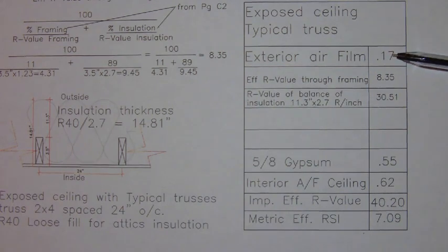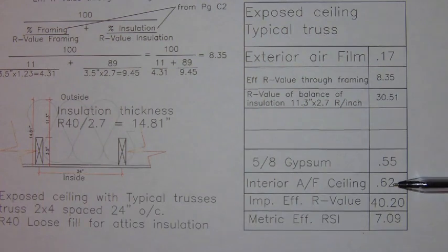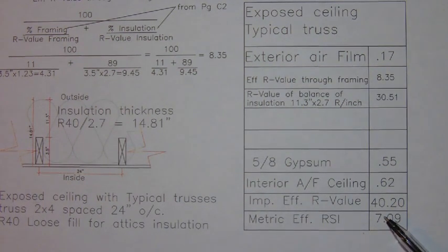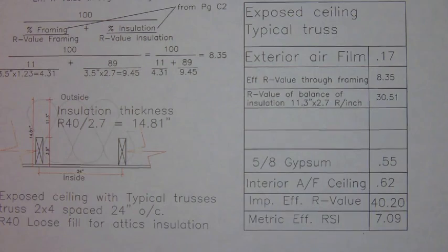Now you can add all those individual R-values, and that gives us a total effective R-value of 40.2 for this particular assembly. The metric equivalent RSI would be 40.2 divided by 5.67, and that will give you 7.09.